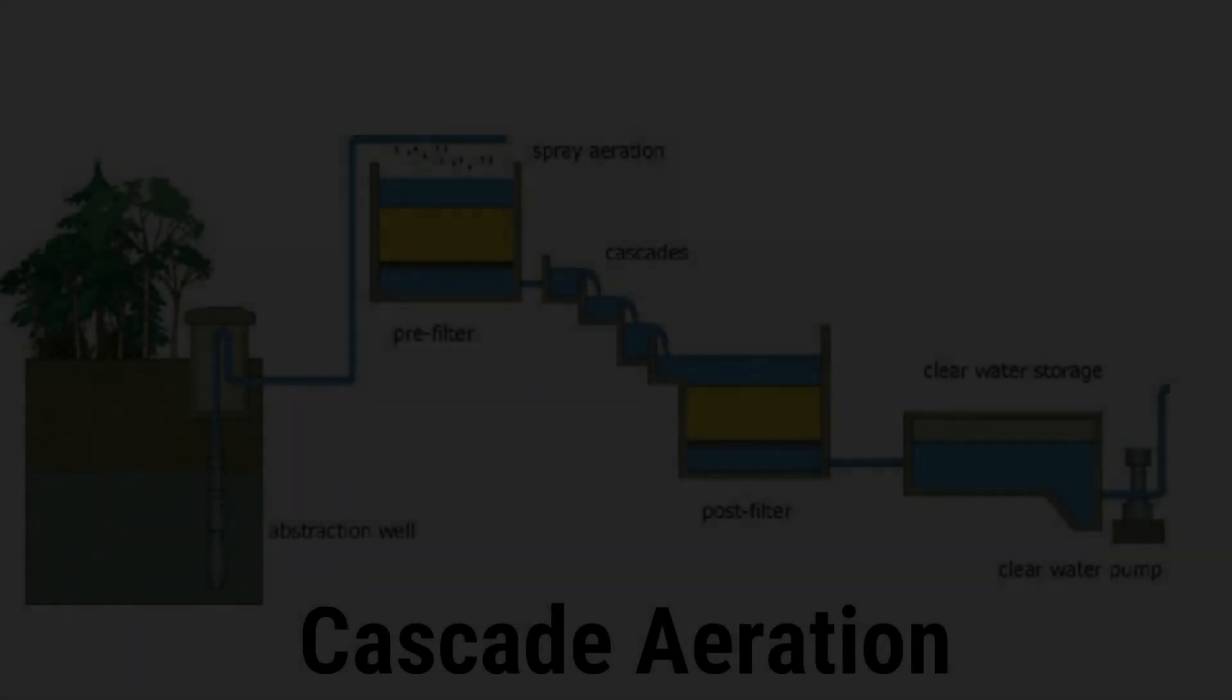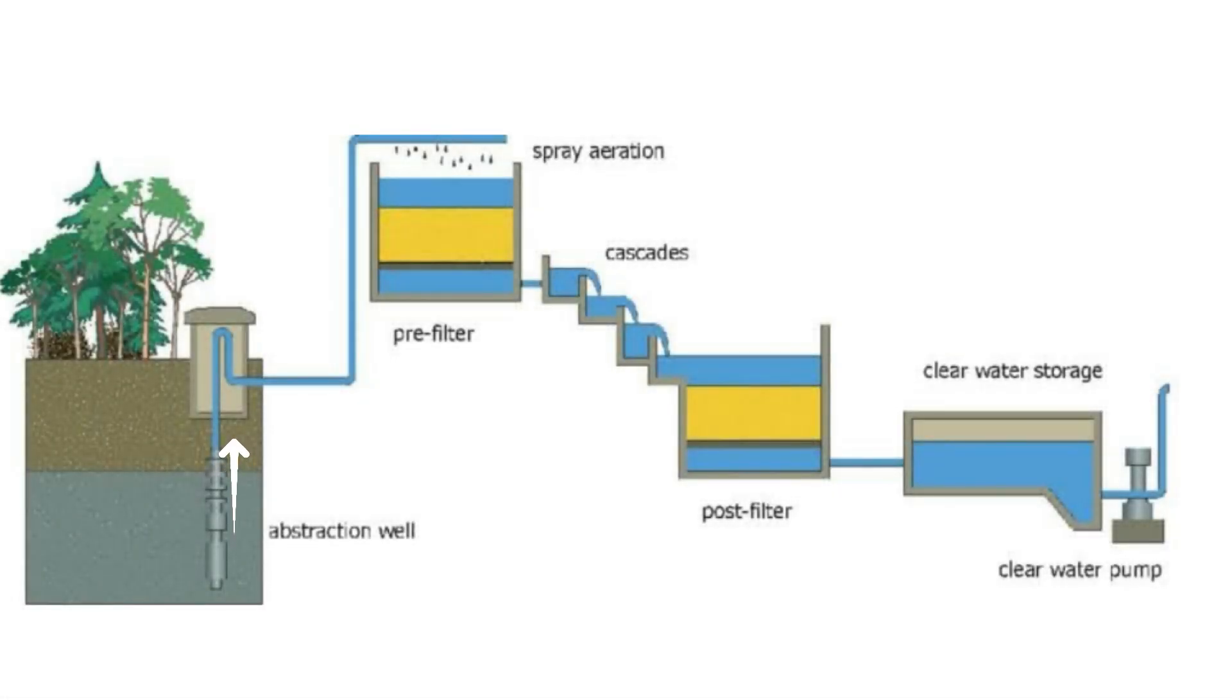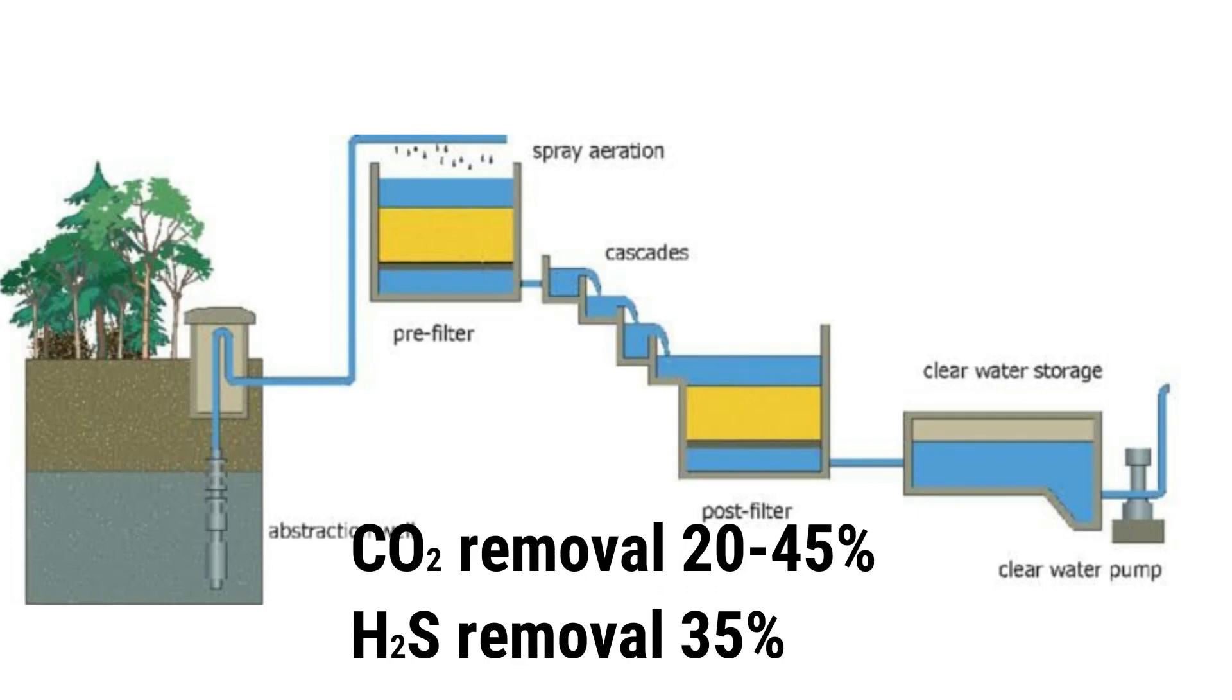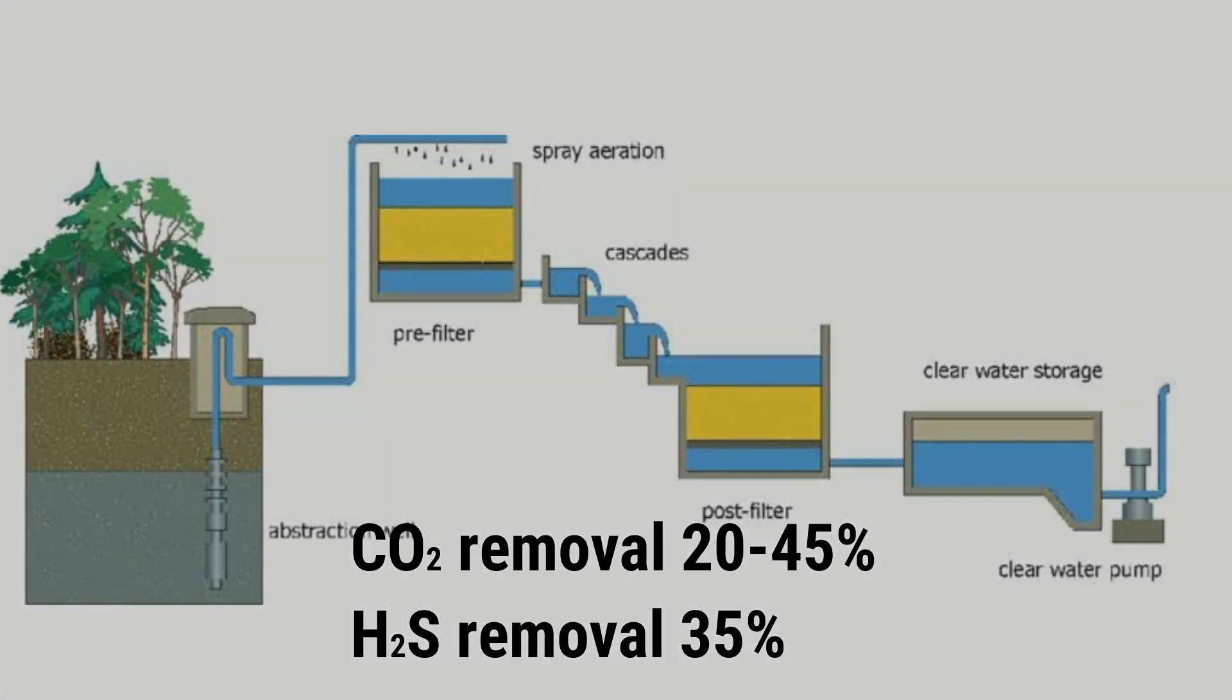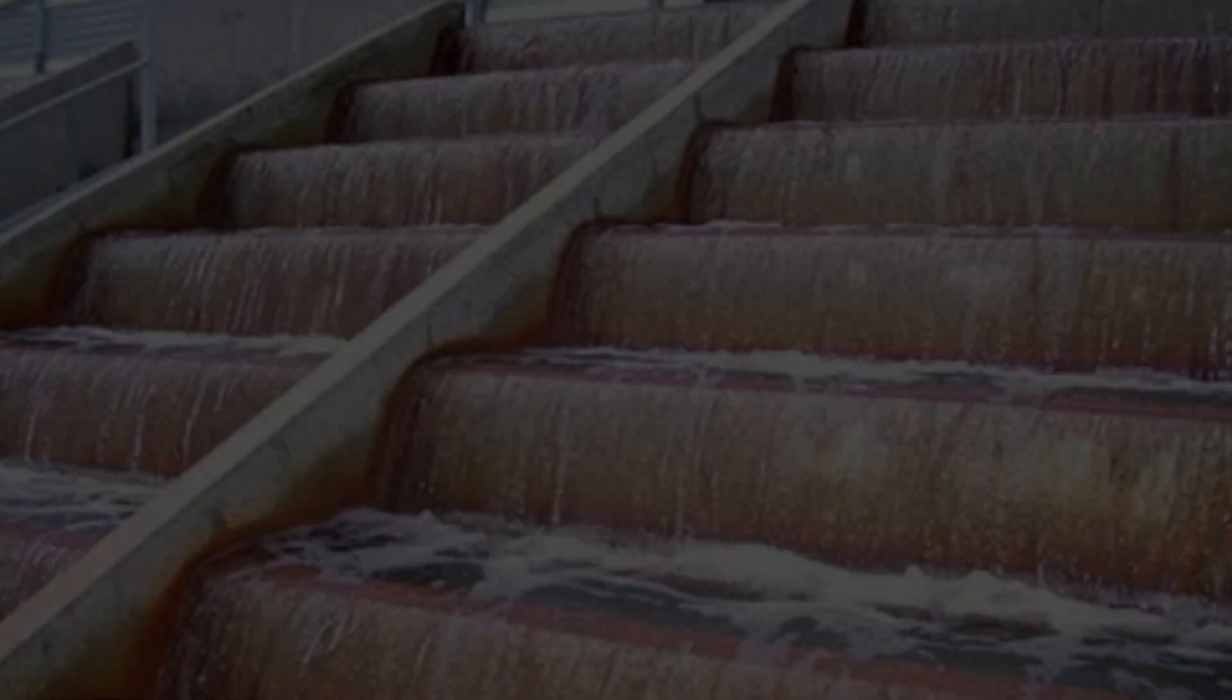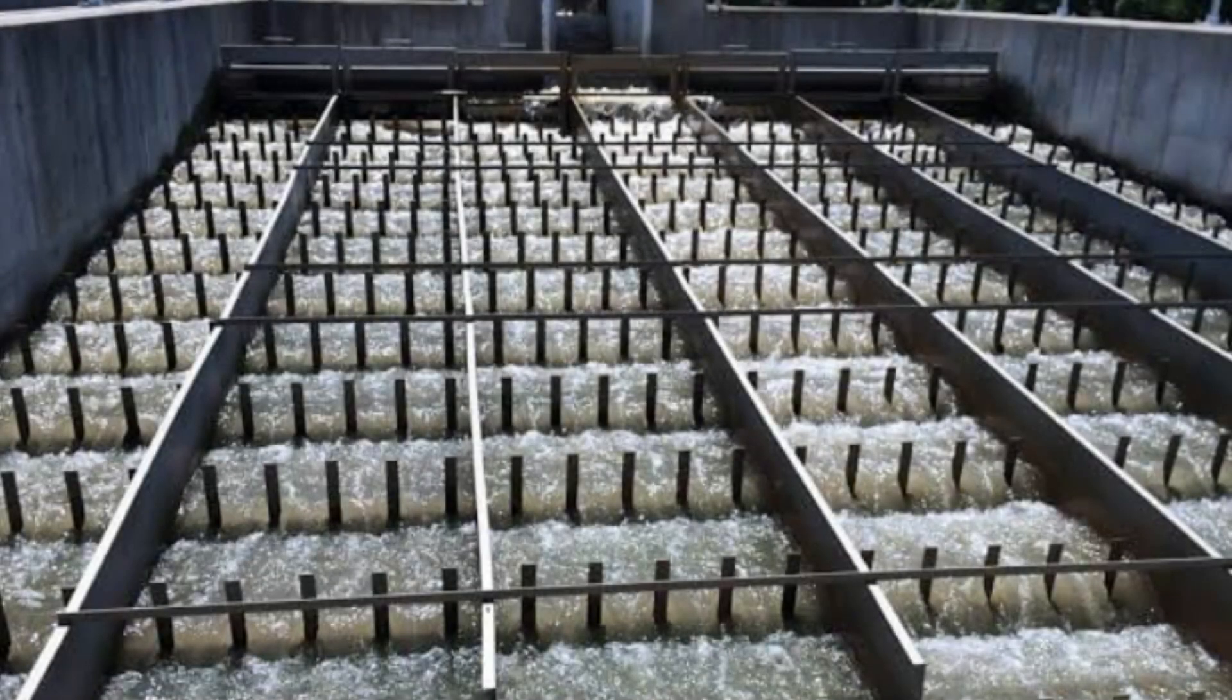This is a cascade aerator system. You can see the water from the abstraction well is pumped and through a spray aerator, the water is sprayed through this filter. Cascade aeration means gravity aerator because the water is falling by means of gravity and after some post filtration, this water is stored in a storage tank. CO2 can be removed by 20 to 45% and H2S can be removed by 35%.